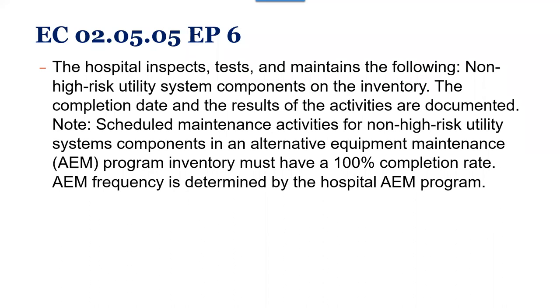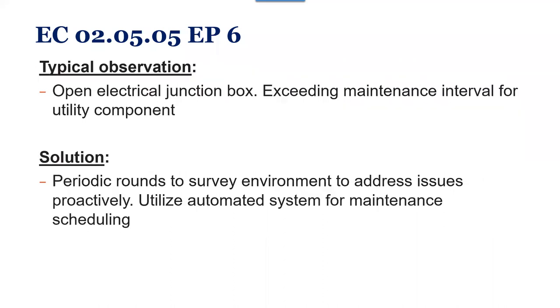EC 02.05.05 EP 6: the hospital inspects, tests, and maintains the following - this is your non-high risk utility system components. Typical observation is open electrical junction boxes, exceeding maintenance interval for utility components. This is the typical, again, periodic rounds to survey environment to address issues proactively, utilize automated system for maintenance scheduling. So those are some solutions for that standard and EP.